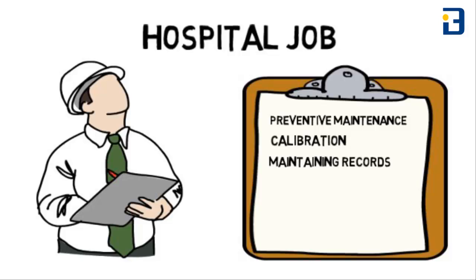The biomedical engineer has to maintain records like equipment history and consumable items. He also has to write specifications for new equipment and machinery, monitor contracts (namely AMC and CMC), and arrange training programs for end users and nursing staff.